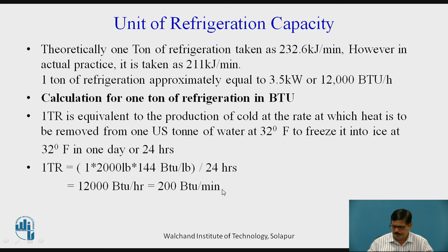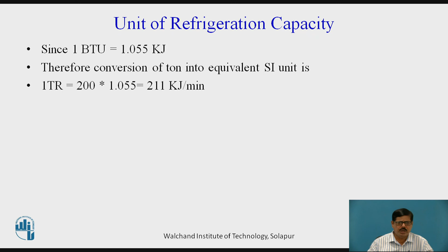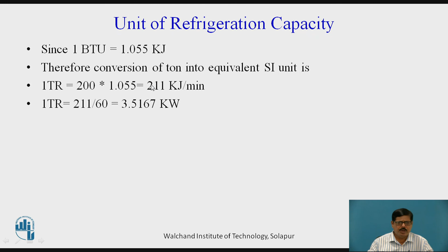If we convert it into SI units, then 1 BTU is equal to 1.055 kilojoules. Therefore, the conversion of ton into the equivalent SI unit is 1 ton equal to 200 into 1.055, that is 211 kilojoules per minute. So, 1 ton is equivalent to 3.5167 kilowatt. This is the actual value which is used in the refrigeration industry. These are the references.